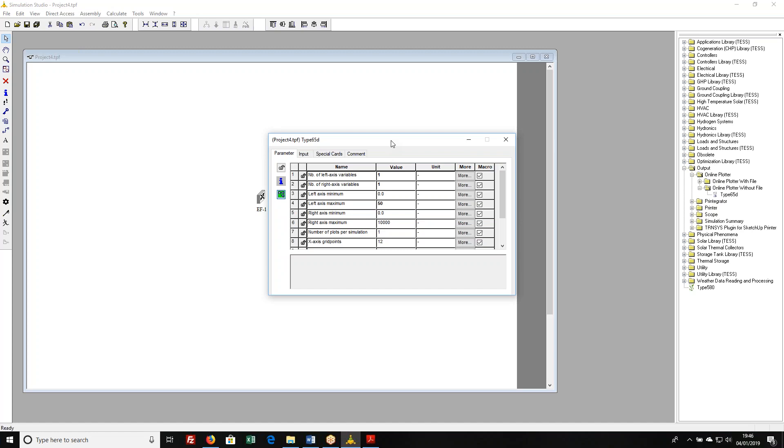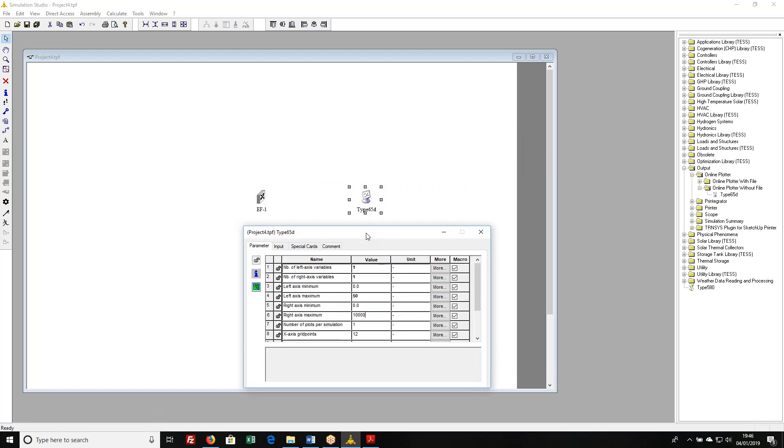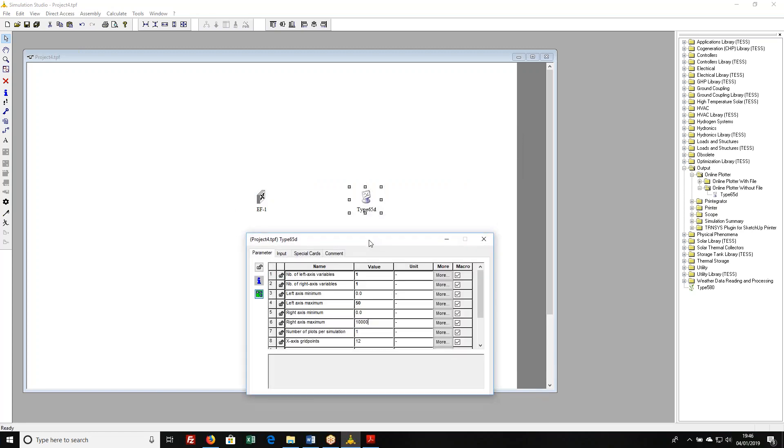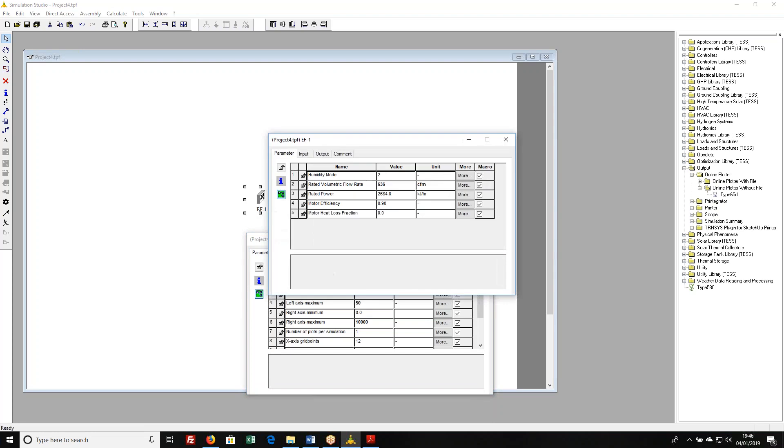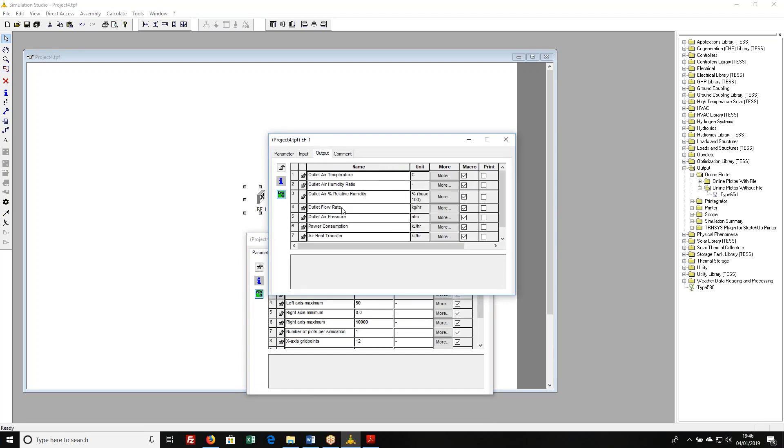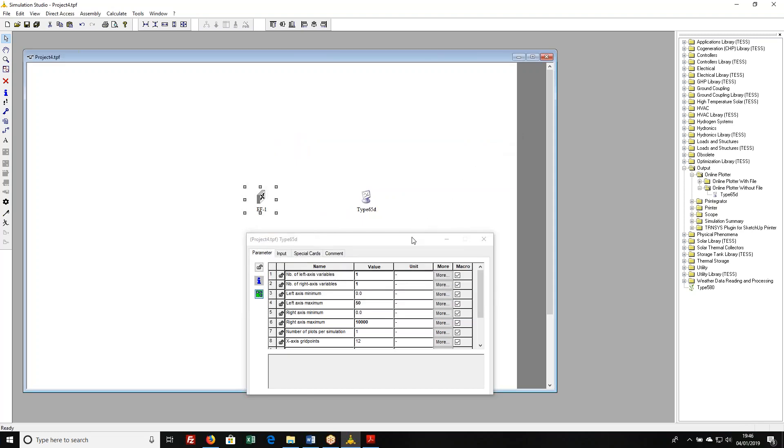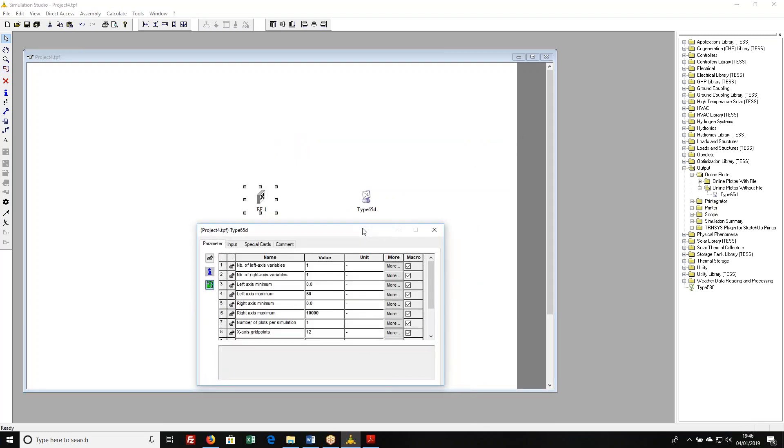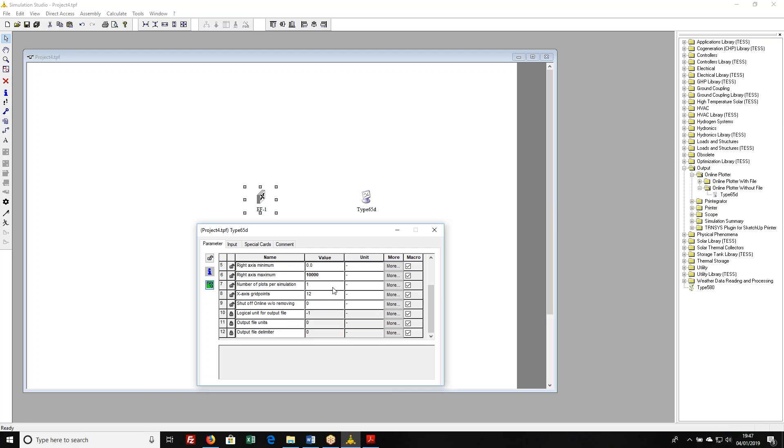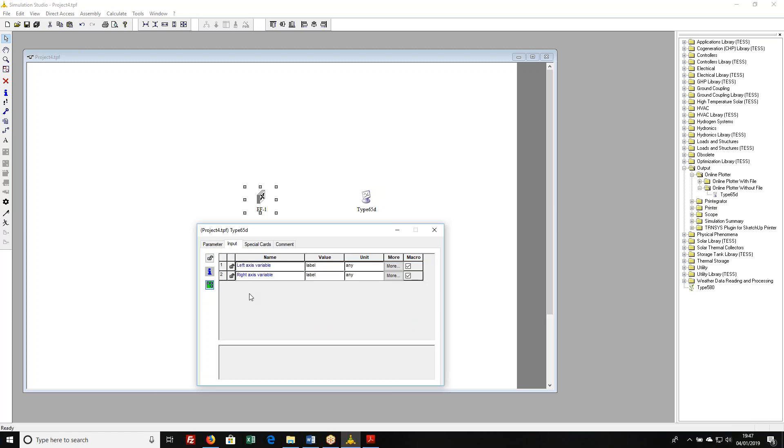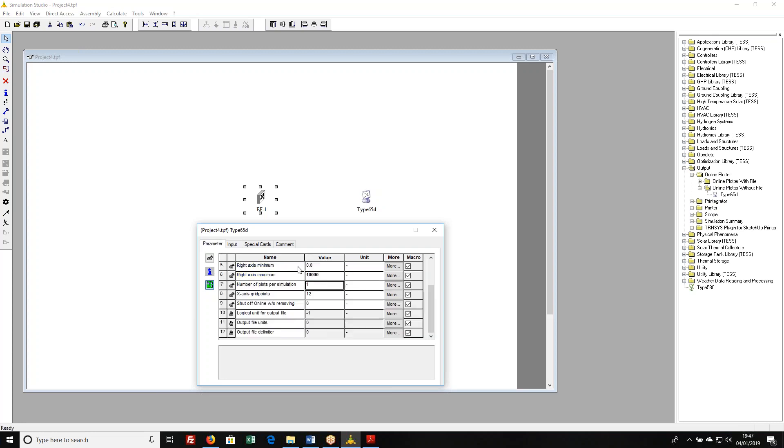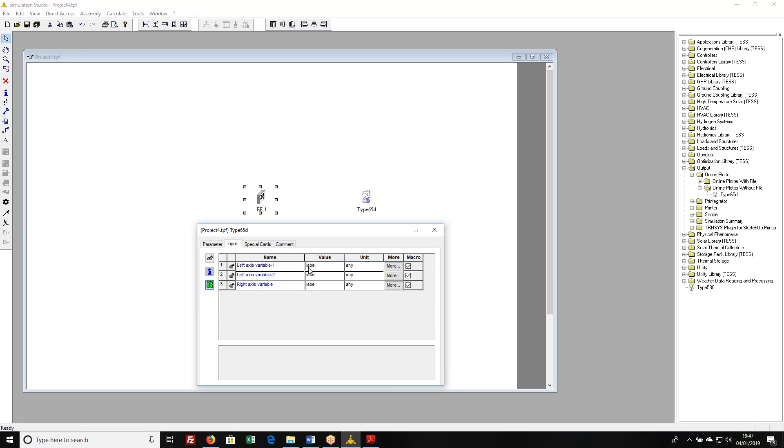On the right axis I'm going to plot my flow rate. And I don't really know what to use here so I'm just going to say 10,000. Perhaps some of you are saying well you set it to be a 635 CFM fan but the output flow rate you'll notice is going to come out in kilograms per hour. I don't really know what 635 CFM equates to in kilograms per hour so I'm just going to arbitrarily choose 10,000. A number of plots per simulation. We'll come back and sort of pick these off later. I switch to the input tab. Here it has adjusted this so that I've got one left axis variable and one right axis variable. Now if I had gone back here and I'd said well I want two on my left axis, you'll see that this has now adapted itself to the parameter value that I happened to choose.